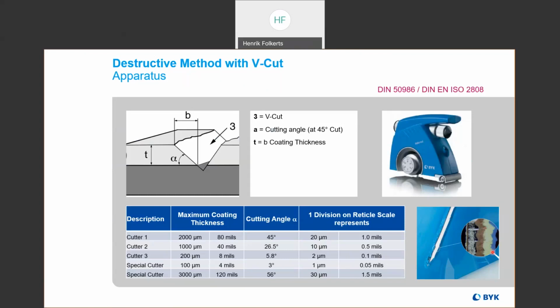You can see that in this image here. Say you're trying to measure the film thickness of this brown coating. You would measure the width using a microscope, and then using the known defined cutting angle, you can convert the width into a depth. And so this is how you measure film thickness destructively.